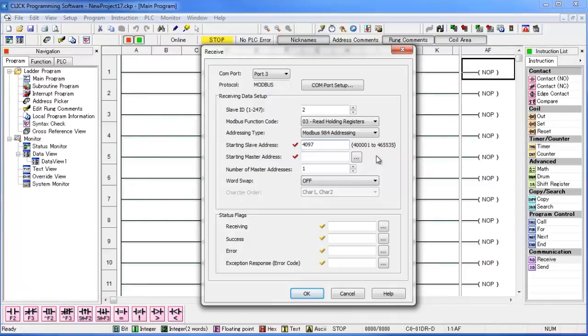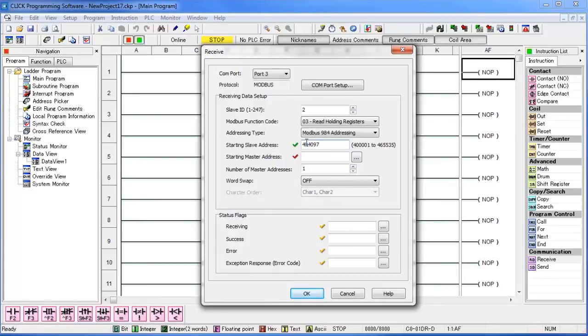So while the desired address is actually 4097, we have to put a 4 in front to denote it as a holding register. And because CLICK requires it to be a 6 digit number, we need to put a 0 after the function code and before the desired address.